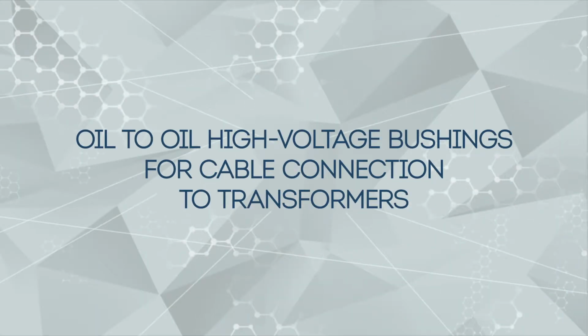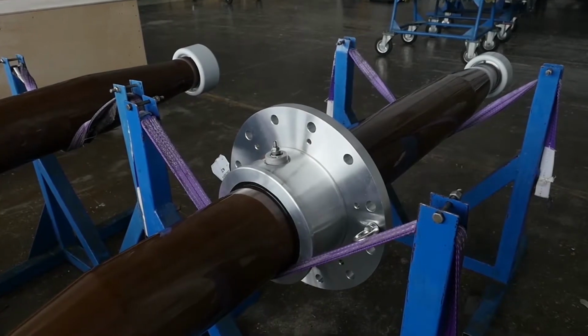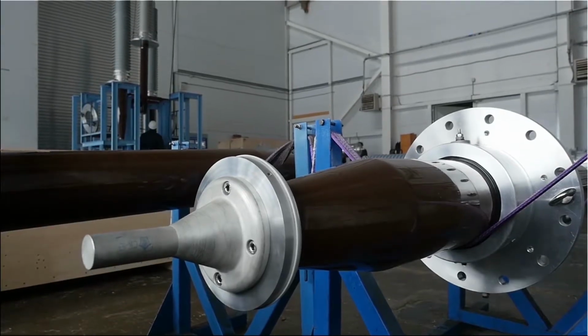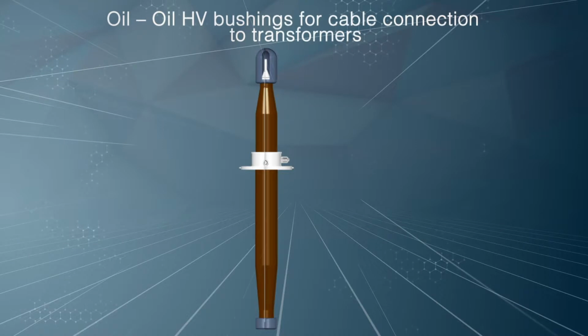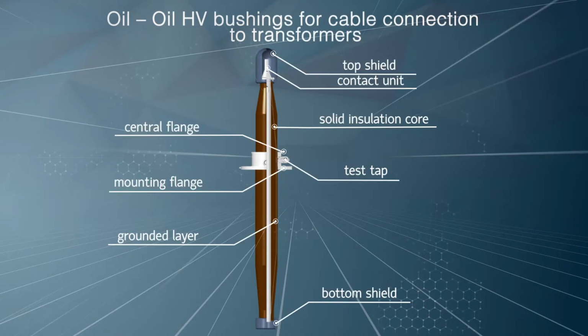Oil-to-oil high-voltage bushings for cable connection to transformers. During operation, the bottom part of the bushing is inside the transformer tank, while the upper one is in the cover of the cable gland. Both parts of the bushing are immersed in transformer oil. Therefore, such bushings are called oil-to-oil. The bushings of the type are peculiar by the absence of external insulation both on the bottom and the upper part of the bushing.